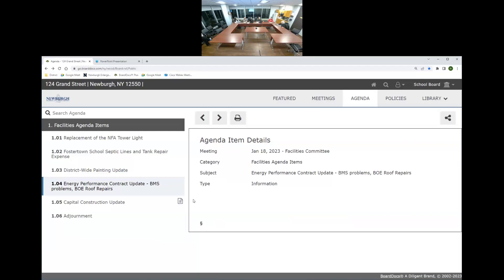Half of the work week is currently dedicated to managing this contract. Each morning starts at Chestnut at 6:45 AM to check classroom temperatures. All classrooms district-wide are set to 71°F, with heating schedules starting at 4:00 AM instead of 6:00 AM so buildings are warm when students arrive. The iPad-based building management system is checked every morning. In this building — NFA — there is both duct heating and radiators; if both run simultaneously temperatures get too high. Johnson Controls must resolve this as it was part of the contracted scope.